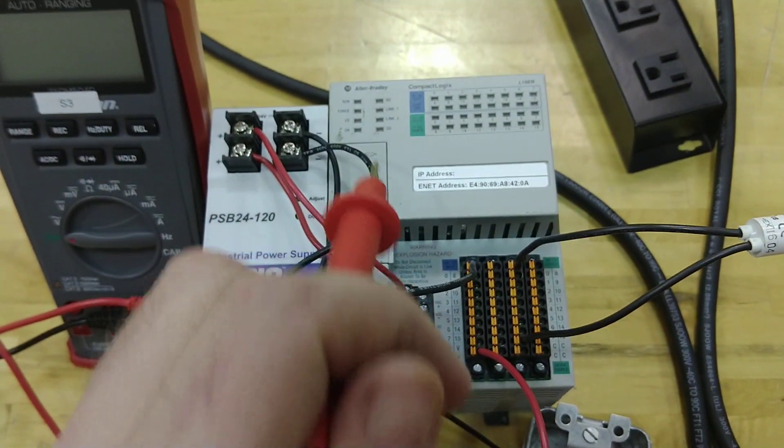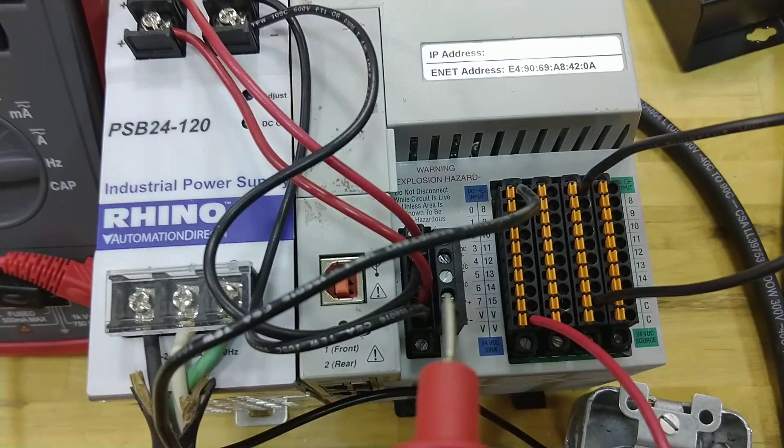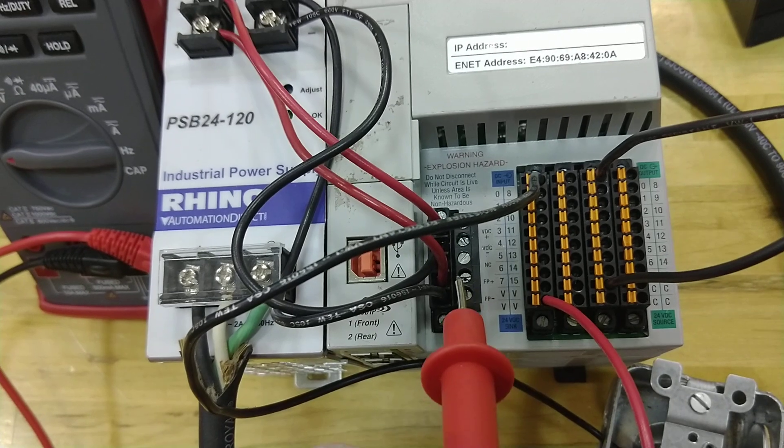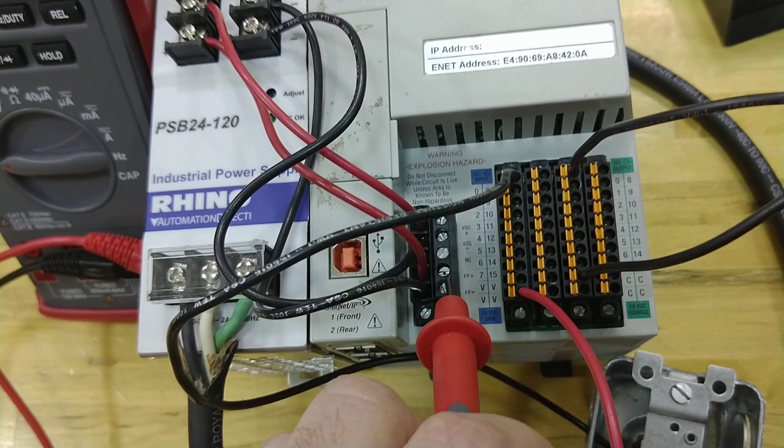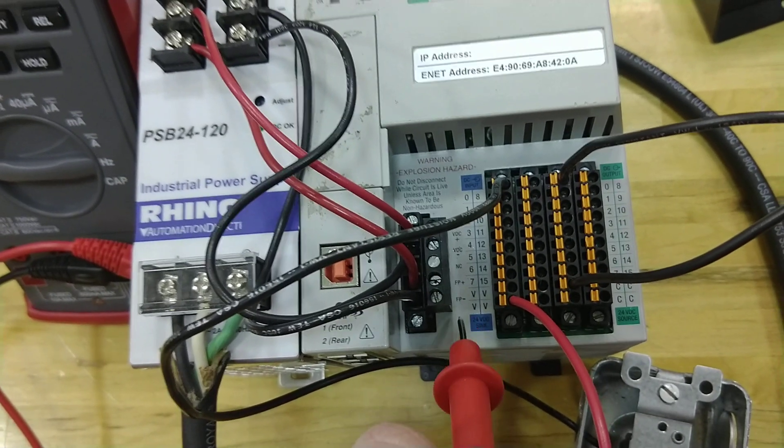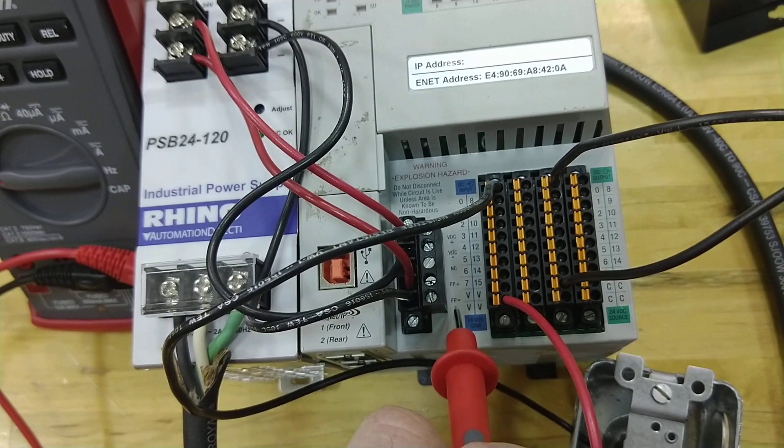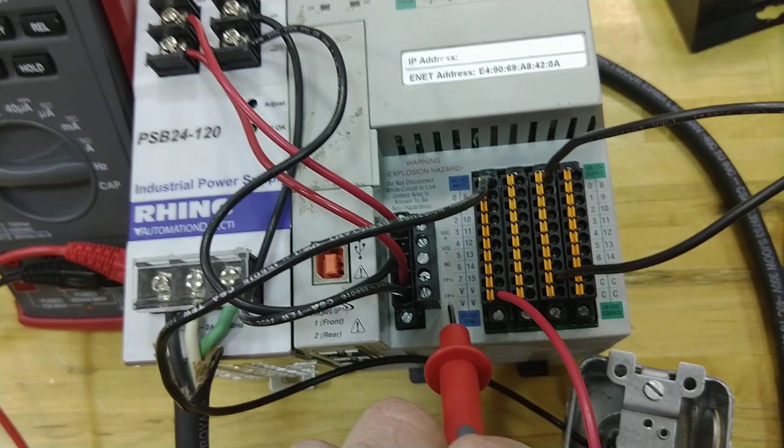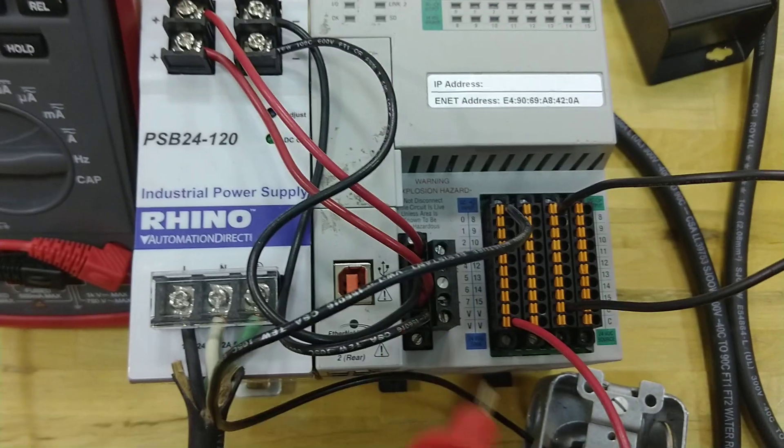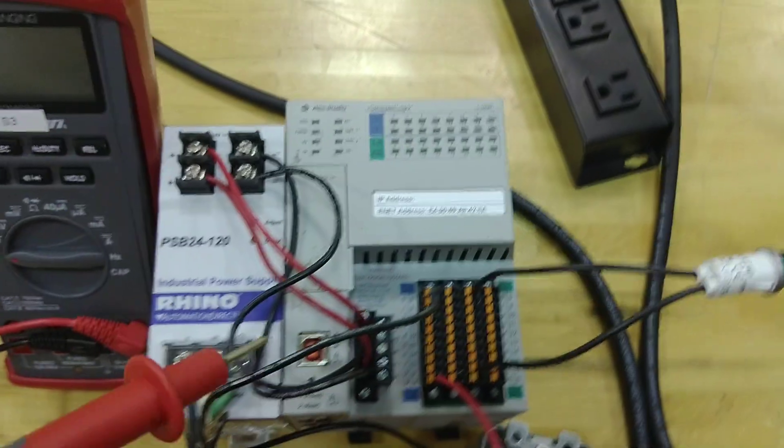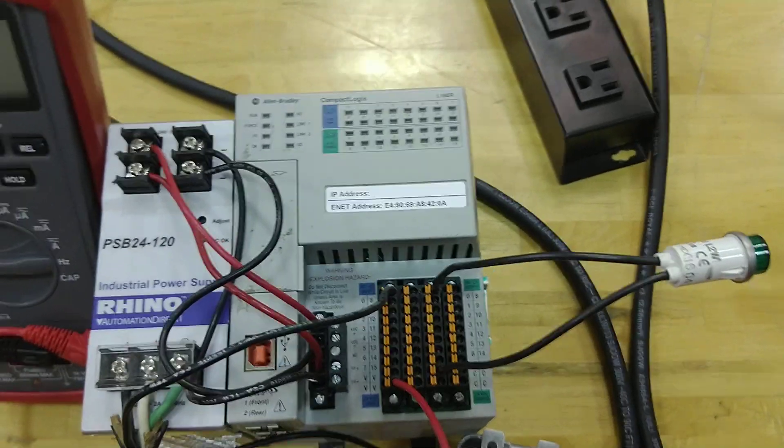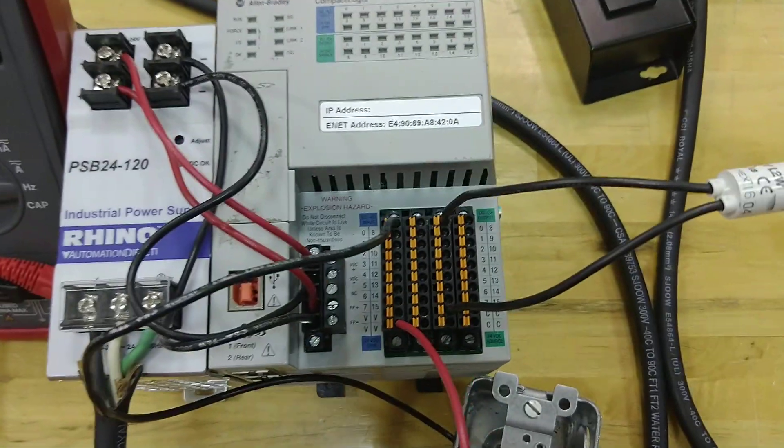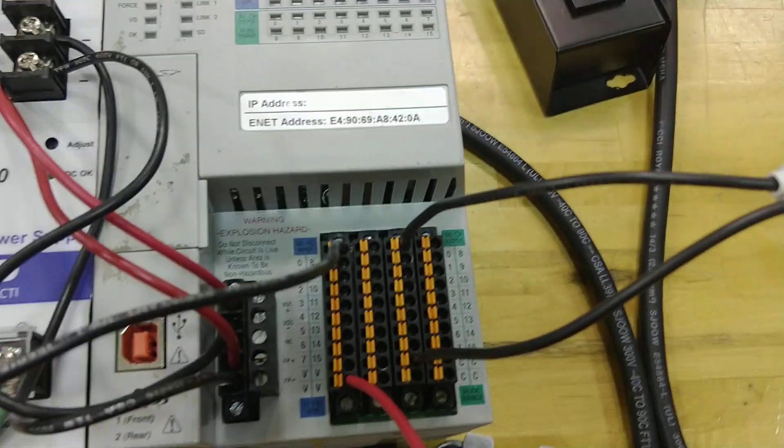So if you wanted to, and many people do this, you could put a switch in between here, because what powers my inputs and outputs are this FP plus and this FP minus. That means field power, positive and negative. So not only do I have to run from both these terminals, and you got to check the tech documents because it doesn't like it if you jumper from these two negatives down on this series of PLC. So you have to run separate. Just keep that in mind.